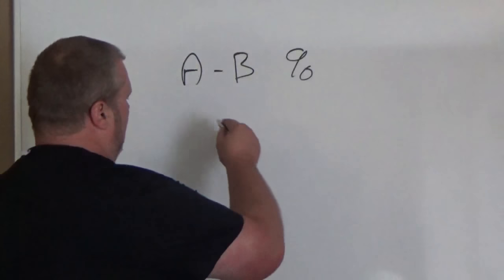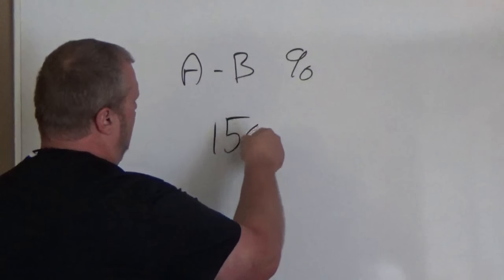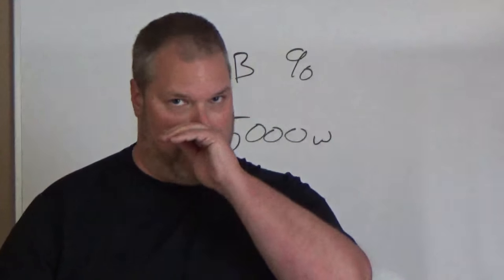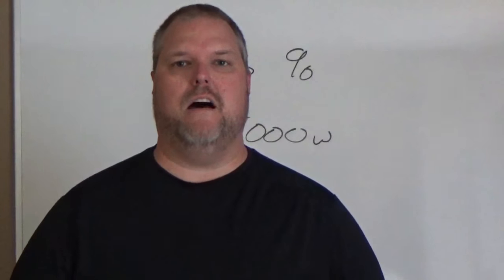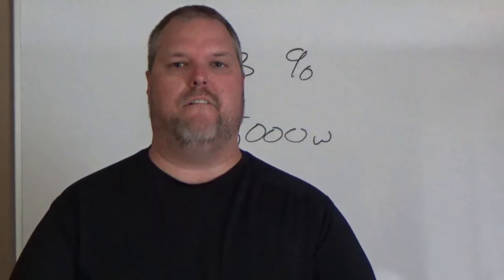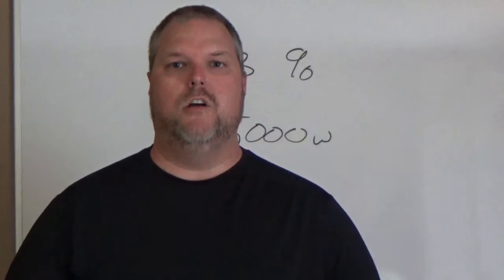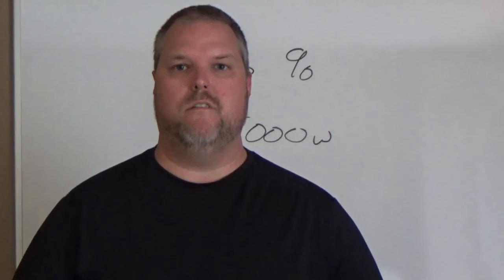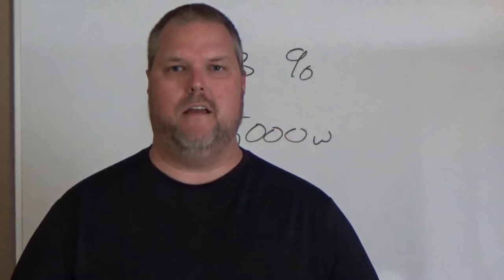What happens if we have something larger than 12 kW? Let's say we have a 15,000 watt range that I'm going to install. Note 1 basically states that for every kW over 12, you have to add 5% to the demand load.